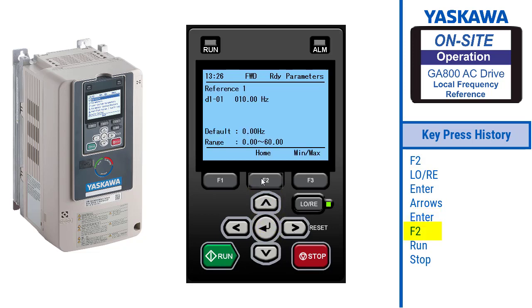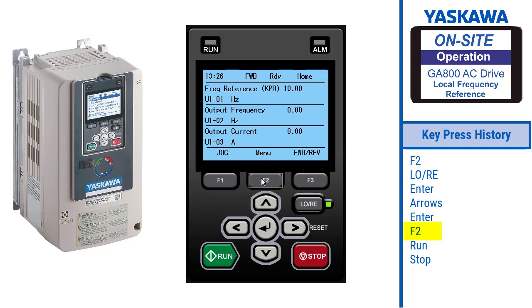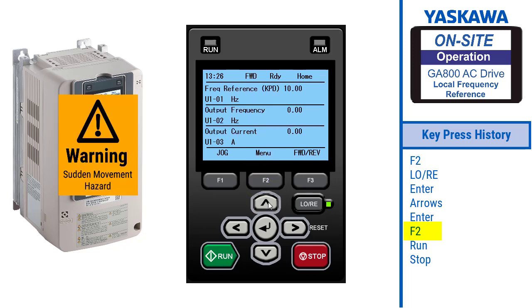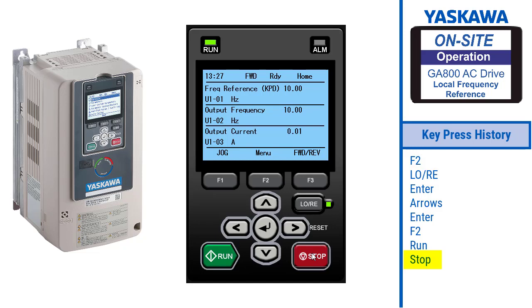Press F2. Make sure the area around the motor or load is clear, as the next step will cause movement. Press RUN. The drive should run, and monitor U102 should display 10 hertz. Press Stop.